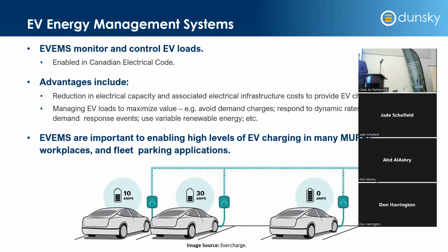Let's say that's a 40 amp, 208 volt branch circuit serving 4 parking spaces. If just one vehicle is plugged in and charging, it can get the full capacity of that circuit and charge at a relatively quick rate, say 50 kilometers worth of charge an hour. If multiple vehicles are plugged in, the charging stations communicate across the network and throttle down their consumption, so you're still just using that 40 amps and not exceeding the circuit's capacity or tripping the breaker. You're slowing down the rate of charging when multiple vehicles are charging simultaneously.